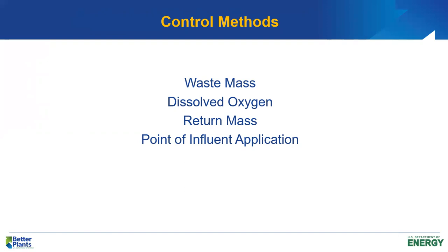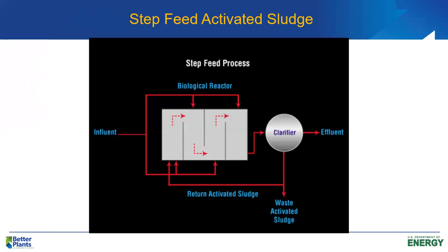Control methods are primarily about waste mass — how much waste sludge we waste from the system each day, measured in flow rate or pounds per day of solids. Dissolved oxygen gives us a little control, but not nearly the kind we get from how much sludge we waste. The return sludge ratio gives us a little control, but again not nearly as much as the waste mass. The point of influent application matters too — if we have a step feed activated sludge process, we have some capability to control where we put the influent in the reactor. Step feed activated sludge is the most flexible type of activated sludge process you can build.